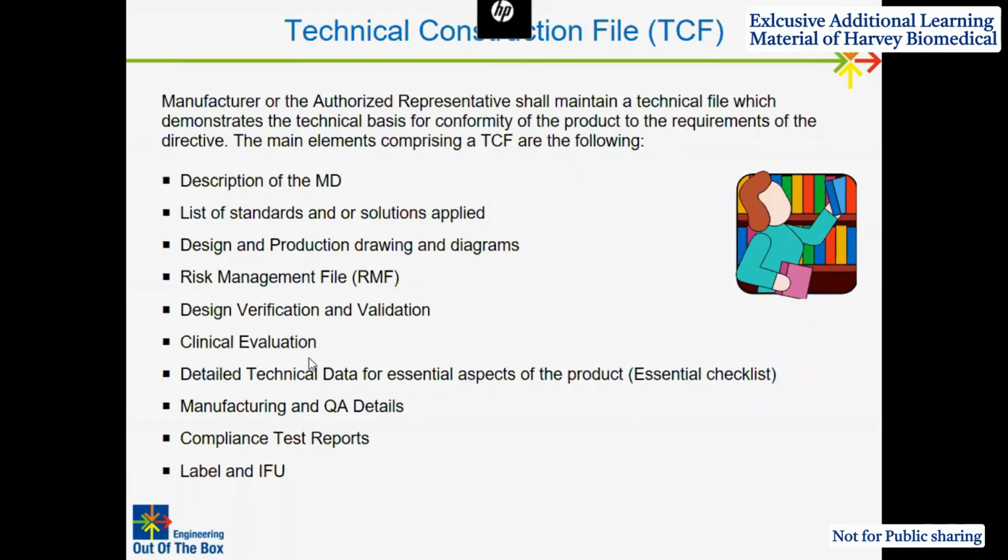Clinical evaluation means clinical evaluation plan, clinical evaluation report, and post-market surveillance, the PSUR, periodic safety update report. All these things we have to cover in the clinical evaluation. And post-market clinical follow-up also. If there is any active implantable medical device, that also we have to take.